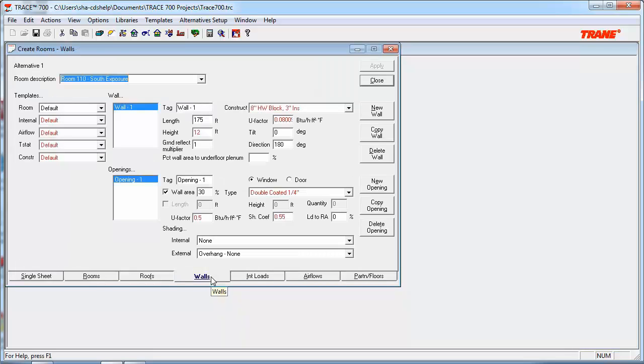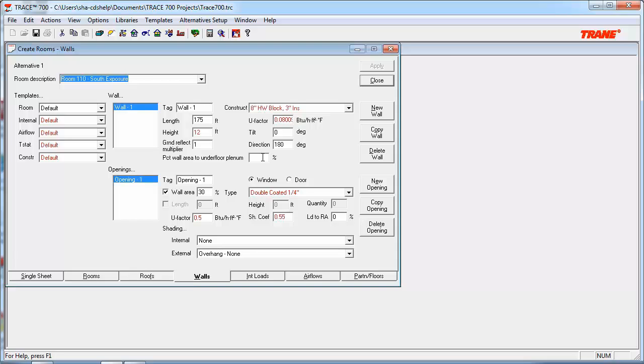There's really only one input to pay attention to here, and it's the percent wall area to underfloor plenum. If left blank, this input will calculate the wall assigned to the underfloor plenum based on the plenum height and the floor-to-floor height. However, if you have a different wall for the underfloor plenum, so as an example, one can install extra insulation on the portion of the external wall below the raised floor in order to minimize the heat transfer, you'll need to use this input.